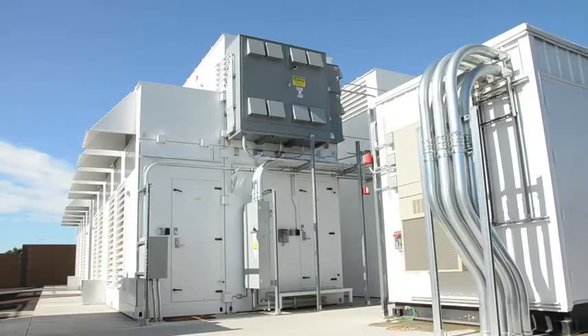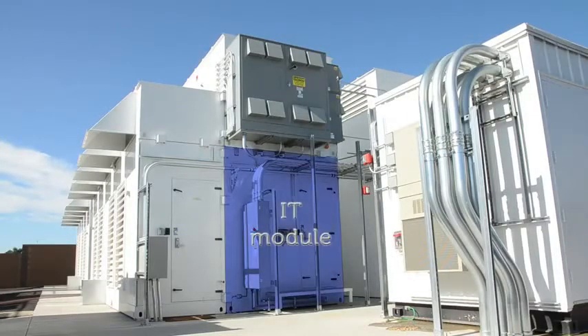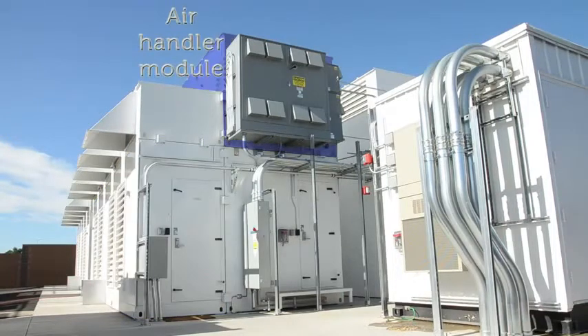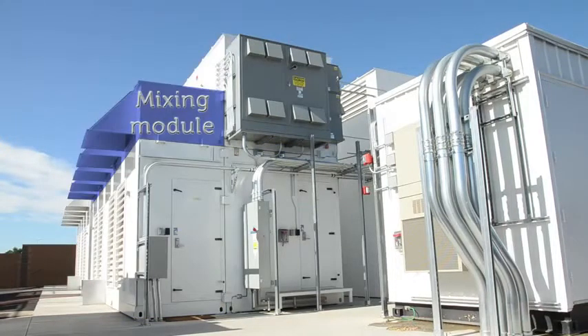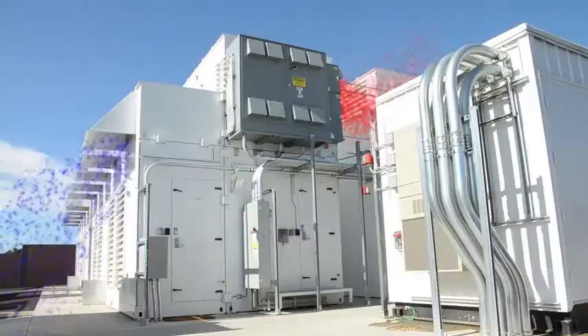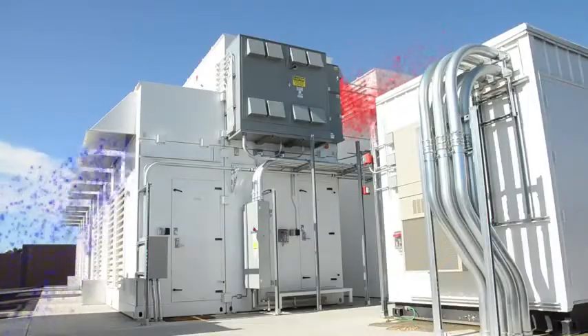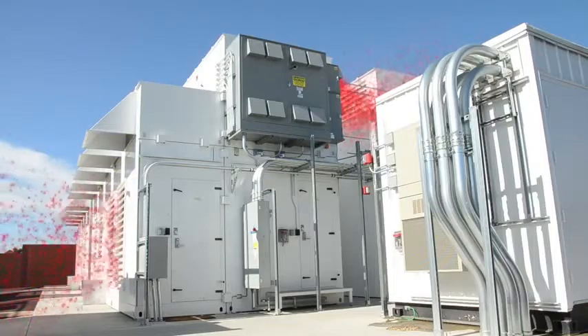The intent or the goal was to right size these modules to do what they needed to do at the most optimized cost. The topology of these modules: you have an IT module, an evap cooling module, an air handler module, and a mixing module. Depending on what condition, how hot or cold it is, dictates what mode of operation this module is in. And so, for instance, today we are actually going between a day cold enough to warrant a mix mode to a warm enough situation where evaporative cooling is turned on and we're actually cooling in an evaporative mode.